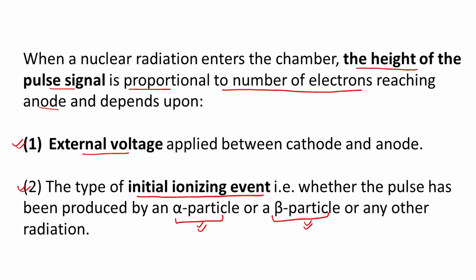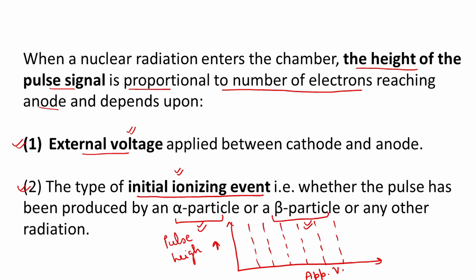The height of the pulse in a gas detector depends on two factors: the external applied voltage, and the initial ionization event. We will discuss how increasing the applied voltage affects pulse height, and also the effect of initial ionization — comparing an alpha particle with high ionizing power versus a beta particle with low ionizing power.